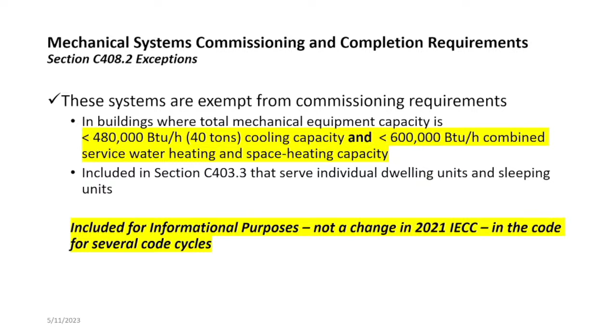also dealing with humidity. Commissioning, and we've talked briefly about this before. Commissioning is not triggered unless the total mechanical equipment capacity is over 40 tons, 480,000 BTUs, cooling capacity, and 600,000 BTUs combined service water heating and space heating. And so unless you have that kind of heating capacity, you don't have to commission.